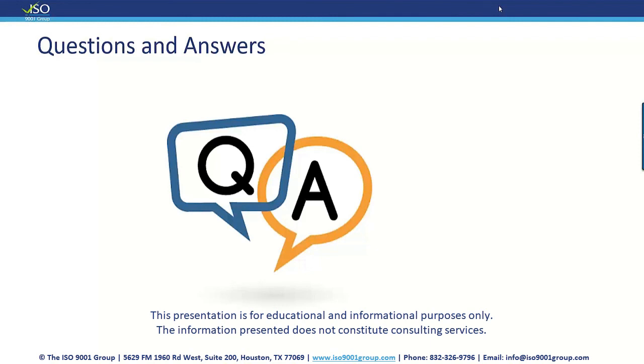Tools that are verified in-house with an NIST standard, should they be called verification certificates? Will auditors question this? No, auditors will not question your verification program. Some may, but again, as I explained in the very first question, you want to make sure your verification program is also following these requirements. I referred you to ISO 17025 as well. So as long as your verification program is very well documented, you have all of these things on your verification report, or you can call it a certificate if you would like.